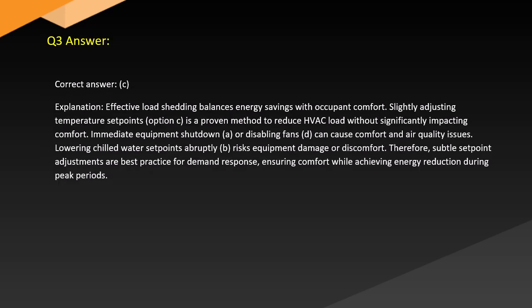Answer. Correct answer: C. Explanation. Effective load shedding balances energy savings with occupant comfort. Slightly adjusting temperature set points, option C, is a proven method to reduce HVAC load without significantly impacting comfort. Immediate equipment shutdown or disabling fans, option D, can cause comfort and air quality issues.